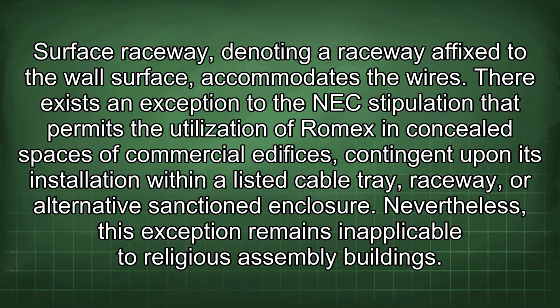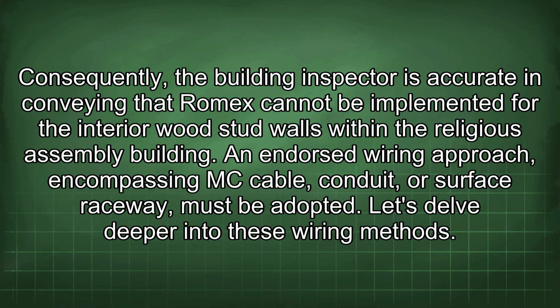There is an exception to the NEC requirement that permits the use of Romex in concealed spaces of commercial buildings, provided it is installed within a listed cable tray, raceway, or other approved enclosure. Nevertheless, this exception does not apply to religious assembly buildings. Consequently, the building inspector is correct that Romex cannot be used for the interior wood stud walls within the religious assembly building. An approved wiring method, including MC cable, conduit, or surface raceway, must be adopted.